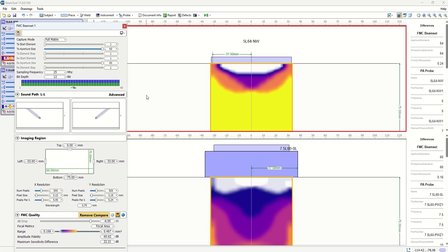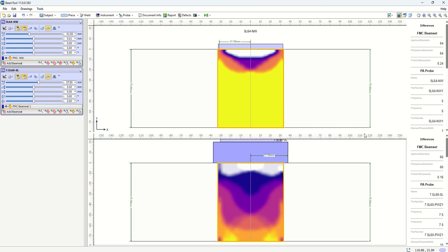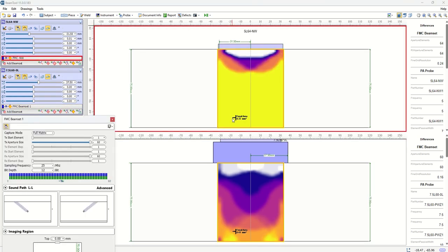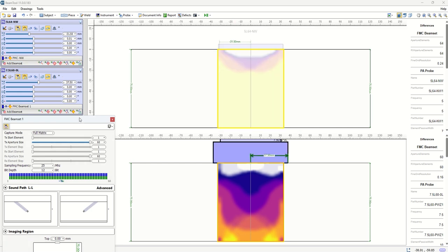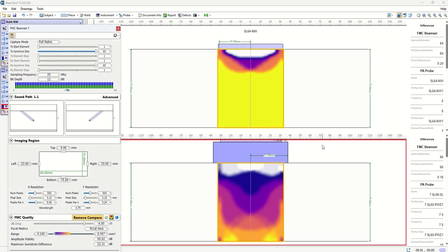Okay, so this is what we see as a comparison of the focal area maps from the top and bottom. The palette that was used, yellow corresponds to larger values, so larger focal areas, and close to white is smaller ones. The top one is contact and the bottom one is the one we want to use. It shows us, surprisingly or maybe even counterintuitively, that the one at the bottom with a wedge actually provides a better, smaller focal area.